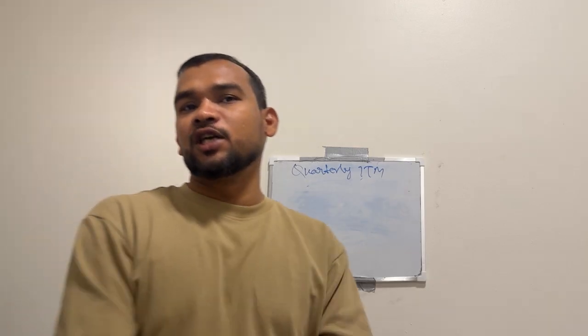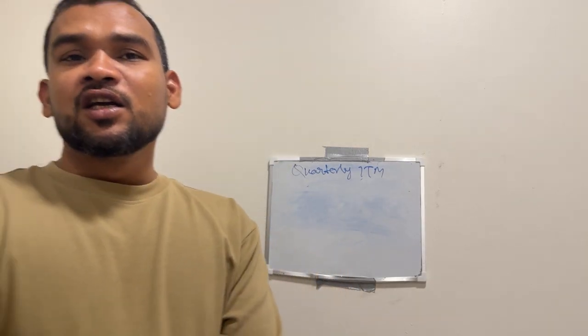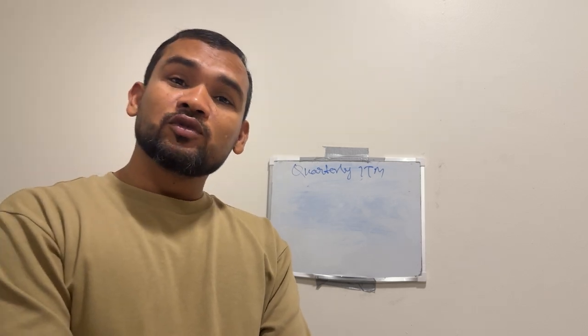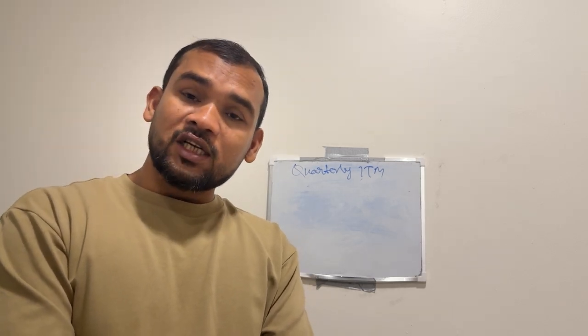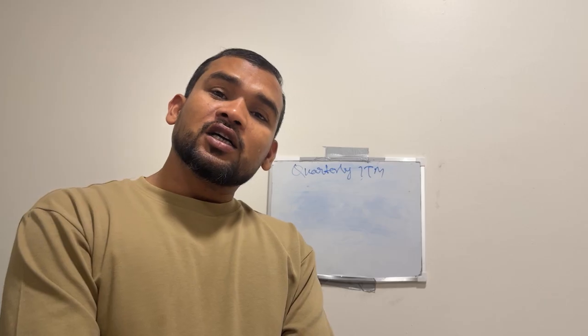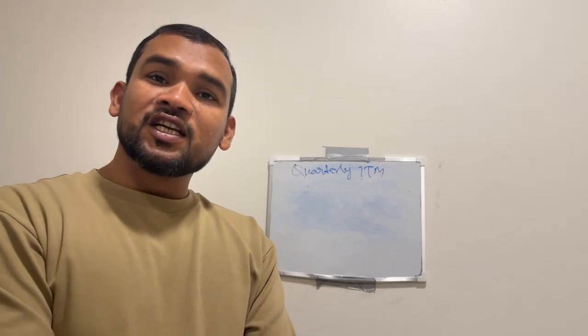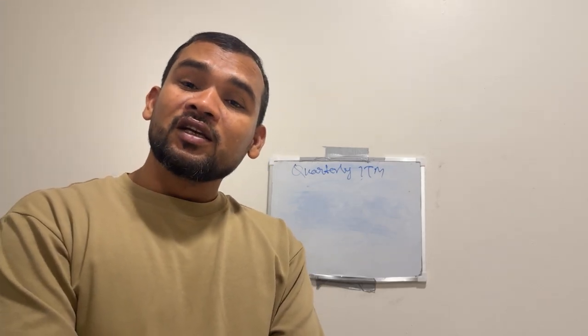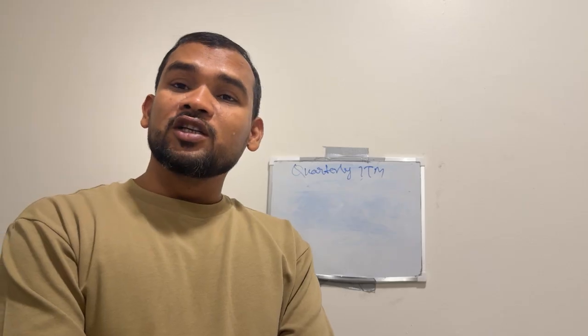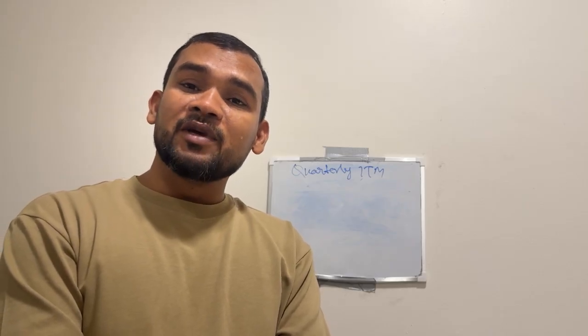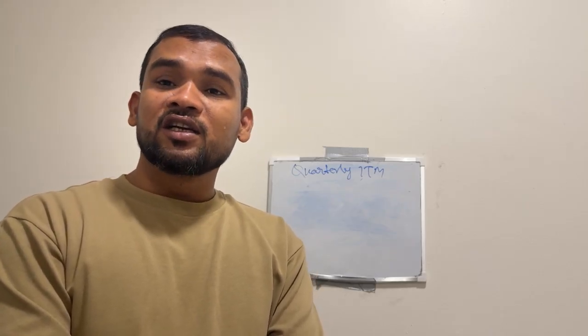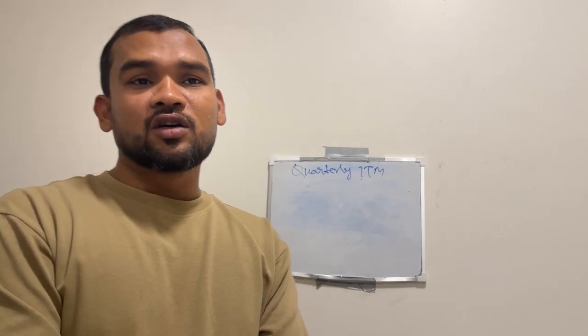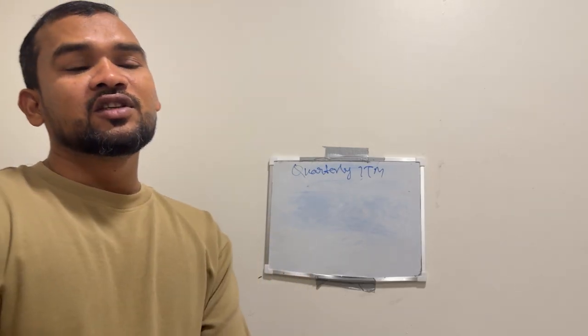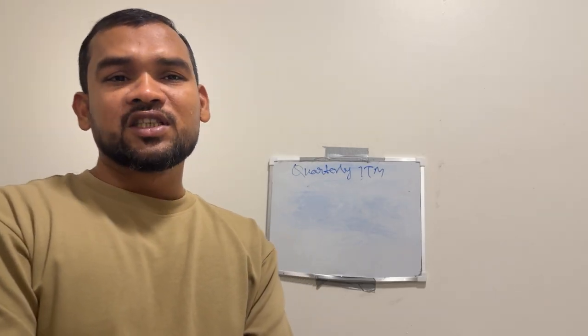Next we have to check the supervisory signal. The supervisory signal is inspected quarterly. What we have to check is that the supervisory signal device is properly installed, there is no physical damage, and there is no obstruction, clearly visible. We have to check all this, and the testing of this is done on an annual basis.